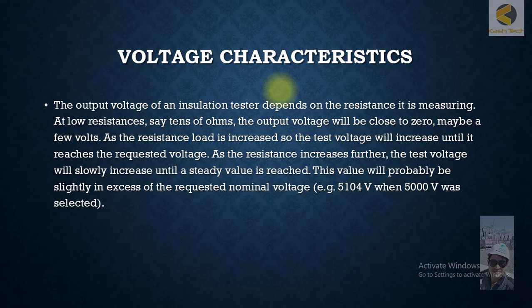The output voltage of an insulation tester depends on the resistance it is measuring. At low resistances, say tens of ohms, the output voltage will be close to zero, maybe a few volts. As the resistance load is increased, the test voltage will increase until it reaches the required voltage. As the resistance increases further, the test voltage will slowly increase until a steady value is reached. This value will probably be slightly in excess of the requested nominal voltage.